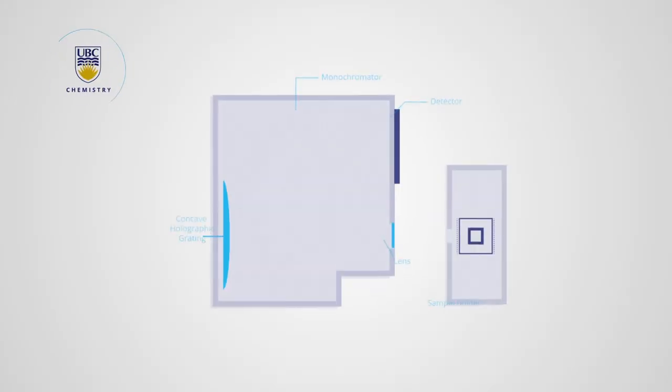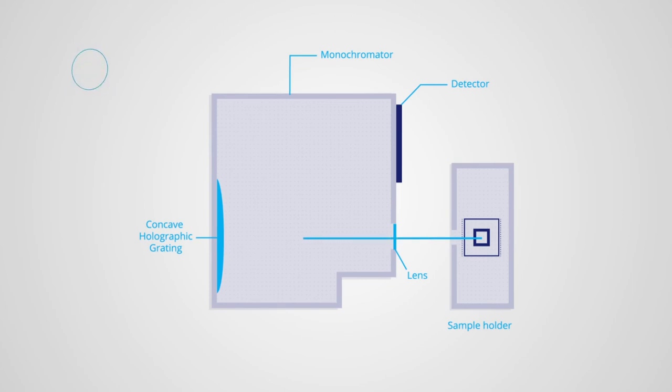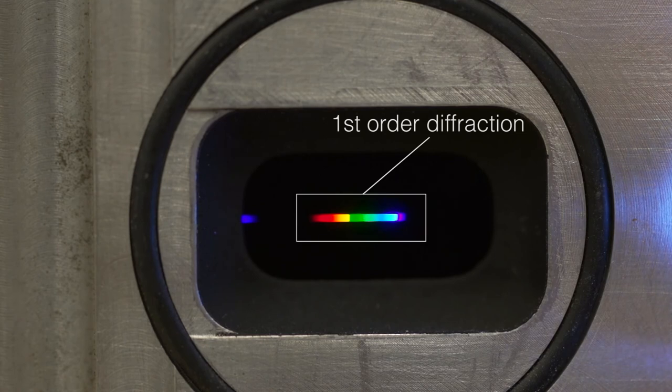The light enters the monochromator through a small lens, and then hits a concave holographic grating. The concave holographic grating disperses the light beam into a strip of its component wavelengths, and focuses each individual wavelength onto a different area of the detector.